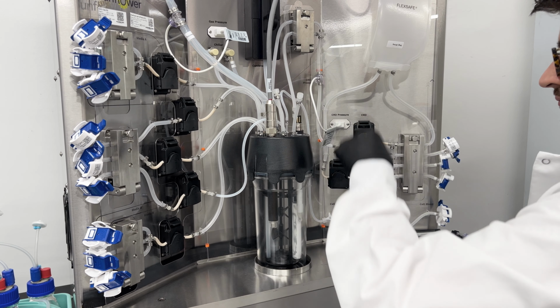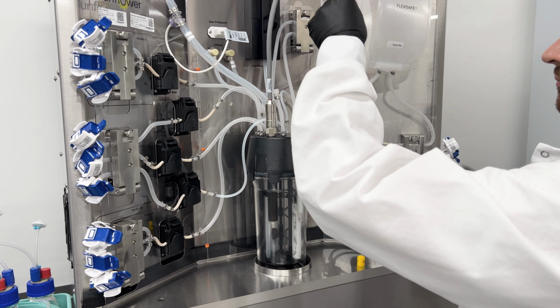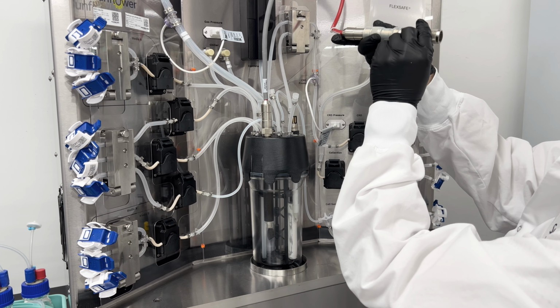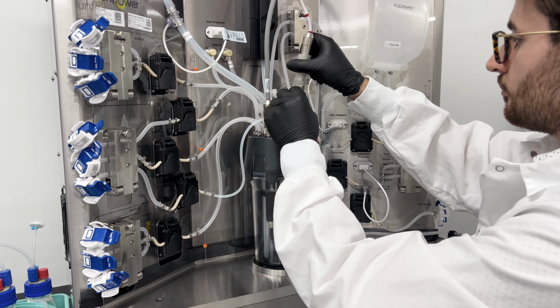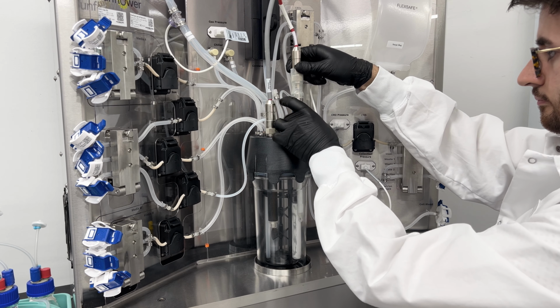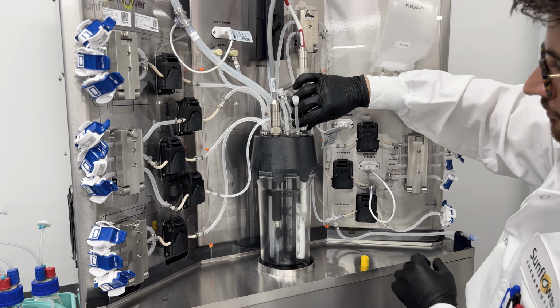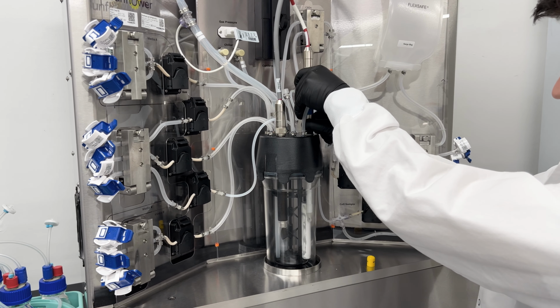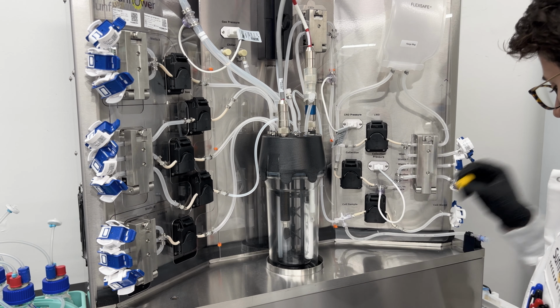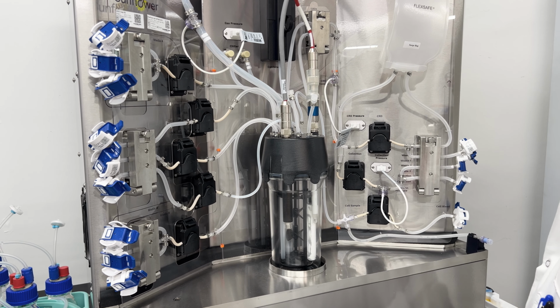To connect the pH cable to the system, we'll remove the yellow cap from the top of the pH probe on the bioreactor headplate and discard it. Place the pH cable connector onto the connector of the probe, turning slightly until the keyed connection catches. Then, finish screwing the threaded collar onto the probe until it is finger tight.